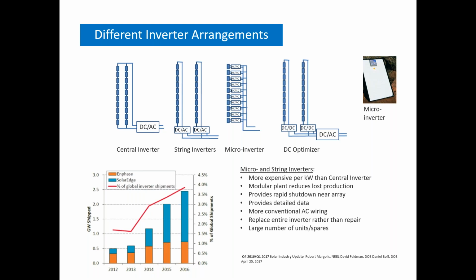String inverters, I'd have an inverter on each string of modules. That might enhance reliability, because when one of the two is down, the other one continues to operate, so I still get half of the production of the plant. And micro inverters put an inverter on each module, and those also enhance reliability for the same reason. It's unlikely that all of them will be down at the same time. And this is also a configuration which is pretty robust to different orientations and shading and other phenomena that can reduce production. And then DC optimizer is a hybrid of that, where I have a DC to DC circuit on each string, and then perhaps a central or more modular inverter plant elsewhere.